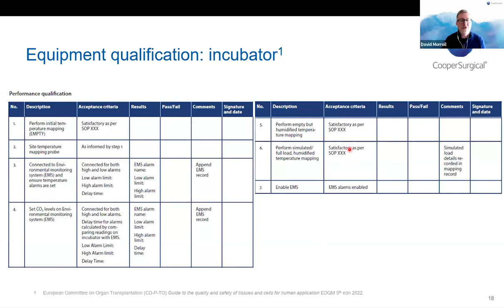at what point do your CO2 levels elicit an alarm? So if you set your CO2 at 6%, does it alarm at 5.9%, 5.8%, 5.5%? You'll need to decide what that low level alarm is, and similarly, you'll have a high alarm limit, and you'll also need to think about delay times. Delay times are really allowing you to go in and out of incubators without always setting off the alarm. You might think about humidification, and you'll also potentially go on and do pH testing, which we'll come on to.